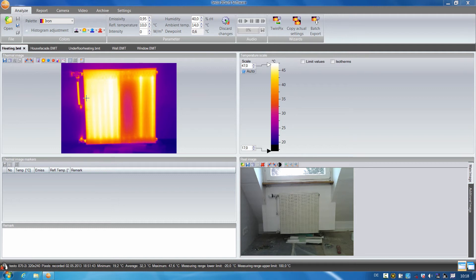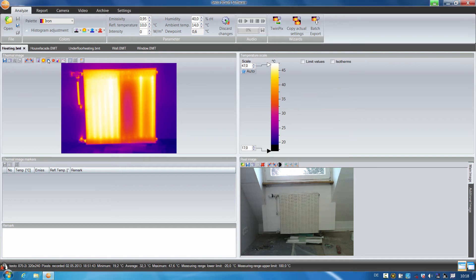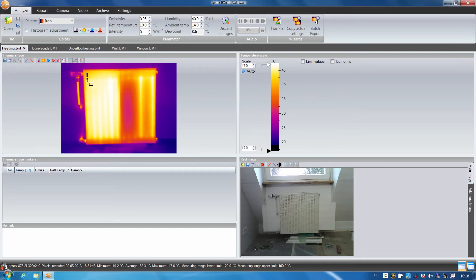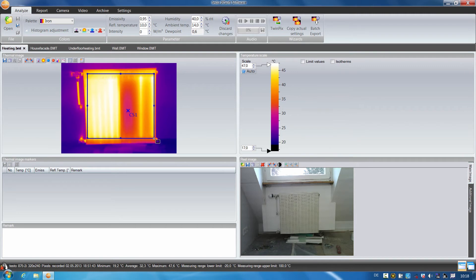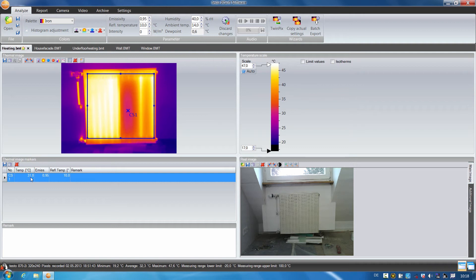With the help of the hot-cold spot recognition, I can clearly demonstrate the temperature difference between the hottest and the coldest point in the thermal image. I start with the cold spot. I mark the area to be examined on the radiator and the spot is immediately displayed. The temperature here is 31 degrees.